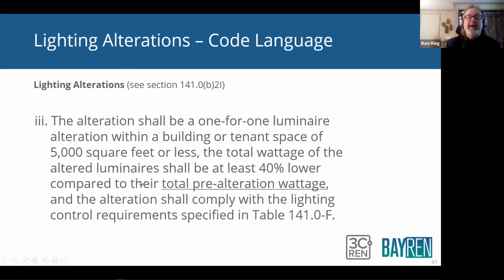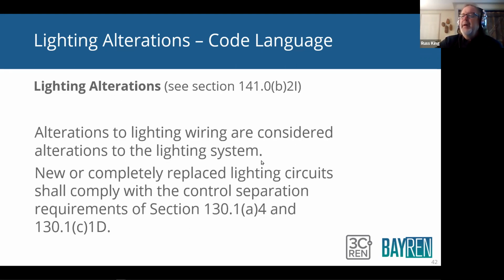And then number three, here's the relamping or the replacing all of the fixtures to make them more efficient. Here's that 40% number. So you've got, what's the wattage before you start? What's the wattage after you're done? If you've improved it by 40%, there's a few little controls you have to meet, but that's that third option. Another thing that's important to understand too is that the wiring for the controls for the lighting and the power for the lighting, if you're messing around with that stuff, that's considered an alteration and potentially can trigger some things. New or completely replaced lighting circuits shall comply with control separation requirements. So just be aware of that.